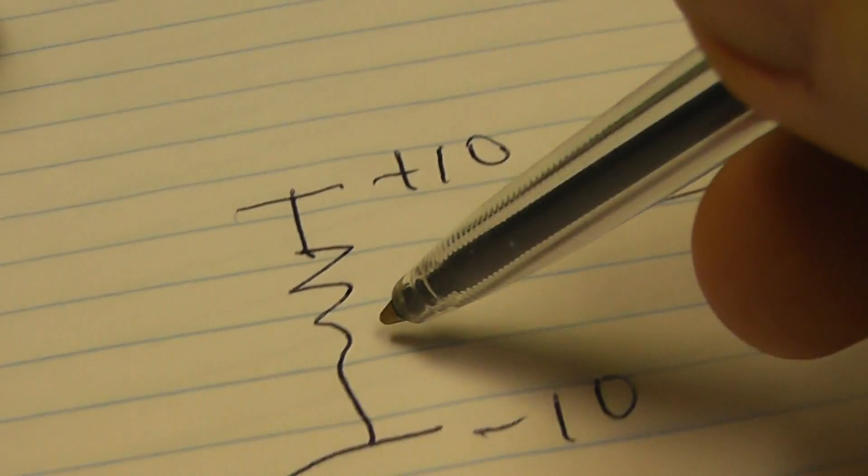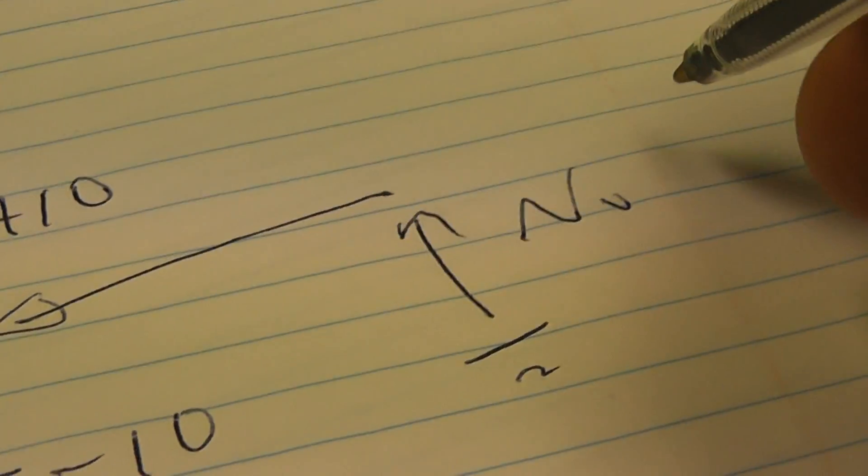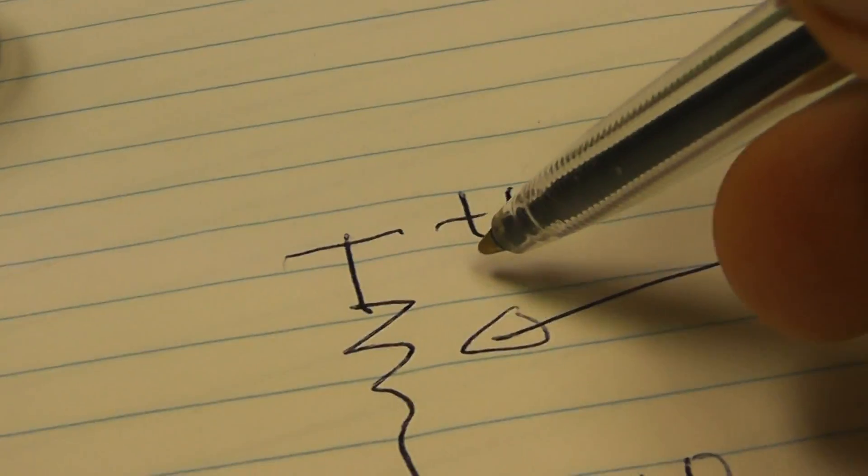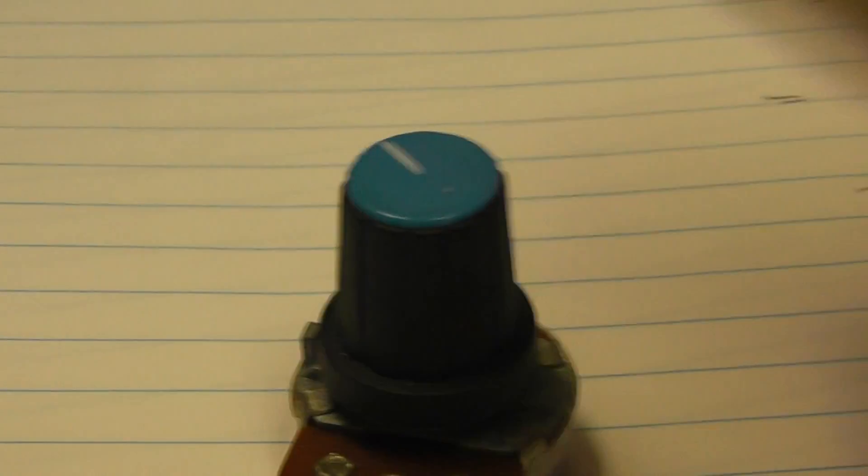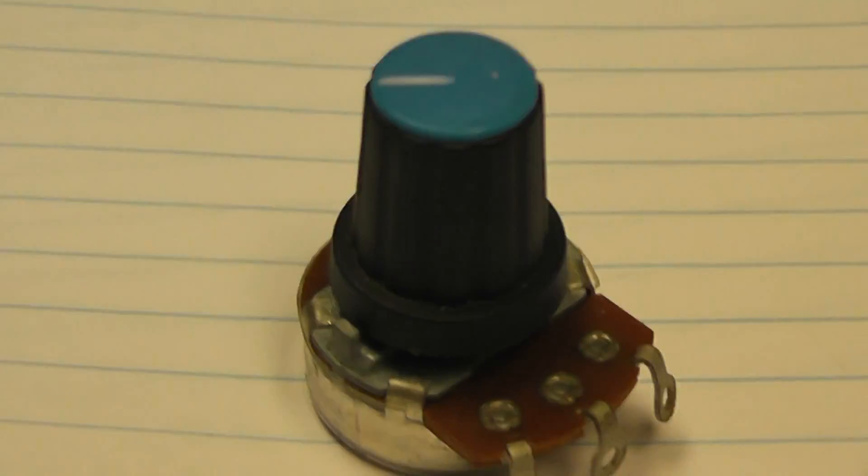So, you'd be doing something like this. Plus 10, minus 10. And we'd take the output here, and that would be V out. Now, if you're set right in the middle, then you get 0 volts out. And if it goes up in that direction, it goes to plus 10 and down to minus 10. And the disadvantage of this is, first of all, it's got a wiper in here and a bit of friction. Although you can get ones that have got much less friction. And secondly, it's limited. It's got an end stop. It can't go beyond that.